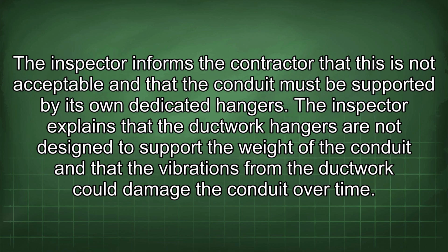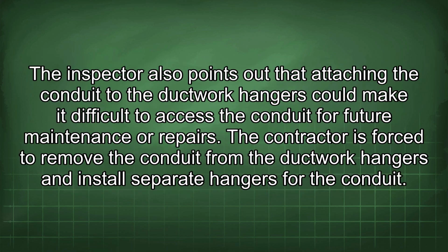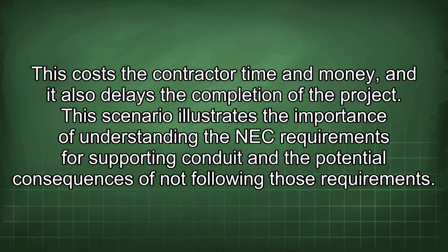The inspector explains that the ductwork hangers are not designed to support the weight of the conduit and that the vibrations from the ductwork could damage the conduit over time. The inspector also points out that attaching the conduit to the ductwork hangers could make it difficult to access the conduit for future maintenance or repairs. The contractor is forced to remove the conduit from the ductwork hangers and install separate hangers for the conduit. This costs the contractor time and money, and it also delays the completion of the project.